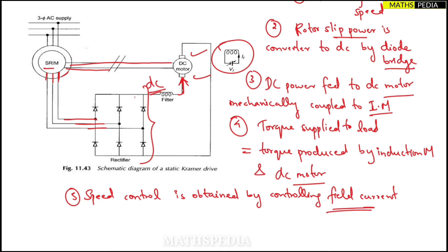Now for large speed range, for large speed variations, instead of this diode bridge we can use the thyristor bridge - we have used in the previous drive, that is Scherbius drive. Thyristor bridge can be put instead of diode bridge for larger speed range variations.